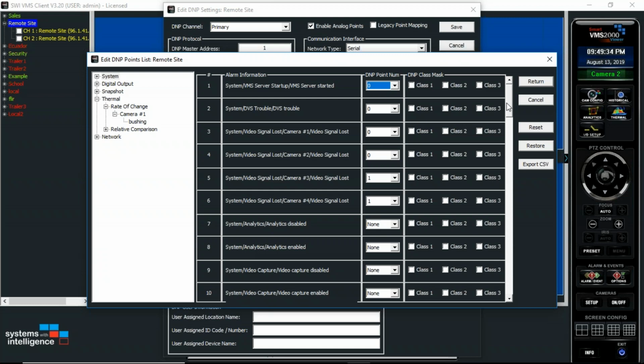Are the status alarm points preset or pre-configured, or can we give our own status alarm? Yeah, that I can explain. Basically, we have here a list of available points that you can choose to communicate via DNP or not. We have many points here. The definitions, we can find out and define later. We have so many available alarms that we can assign.